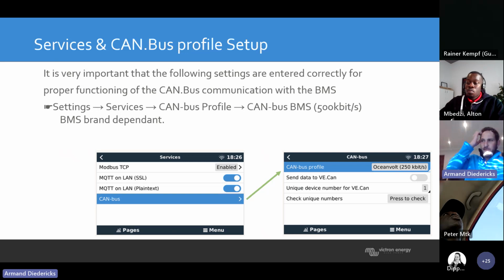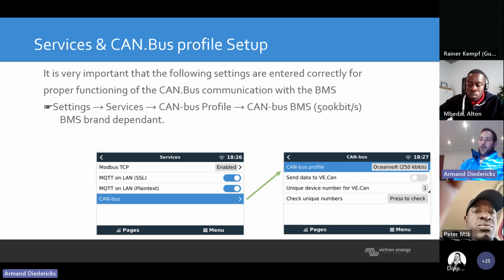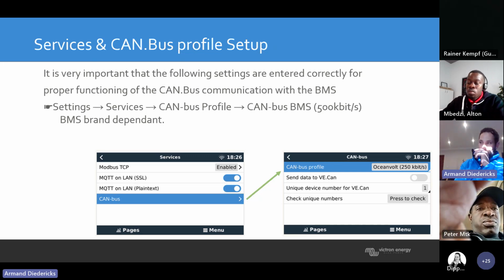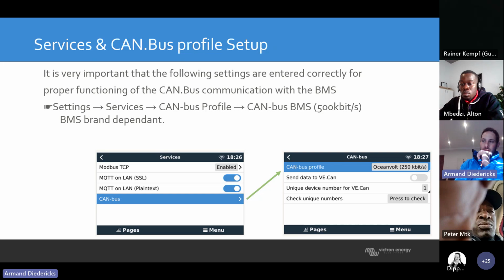All right, services and CAN bus profile setup. This is where you've got multiple different battery BMSs with different protocol types. So it depends on what cable it's running. It's very important that the following settings are entered correctly for proper function of the CAN bus. Settings, services, it's at the bottom of the settings. Services, CAN bus profile, CAN bus BMS, 500 kbit. The old Blue Nova units used to work with 250 kbit.